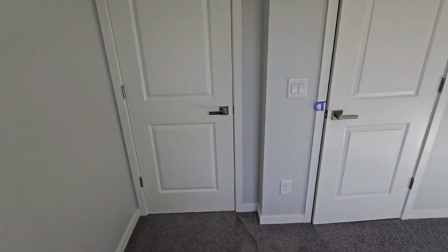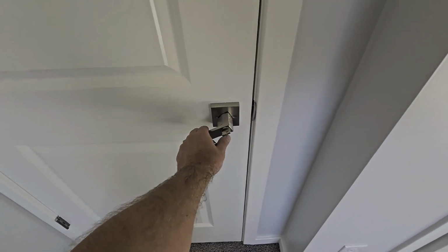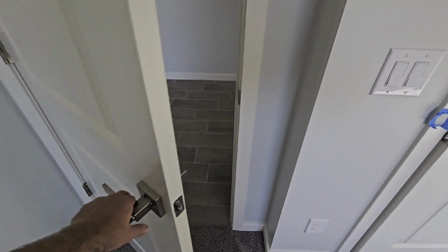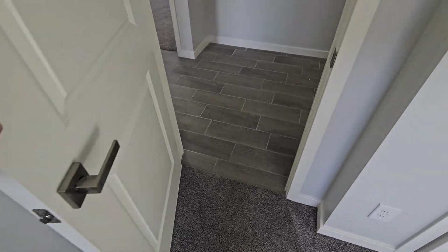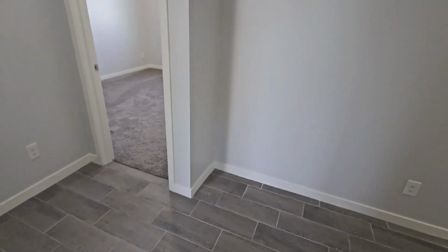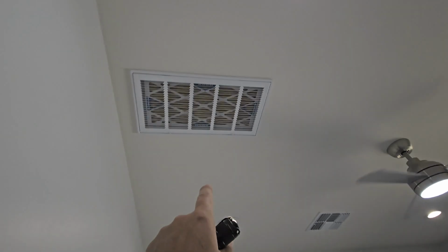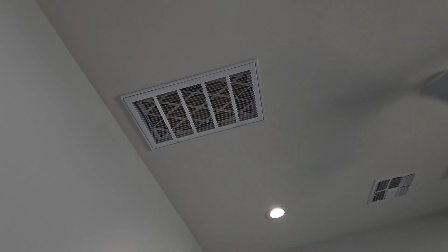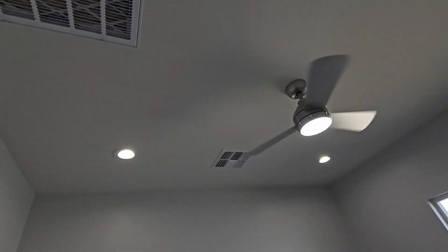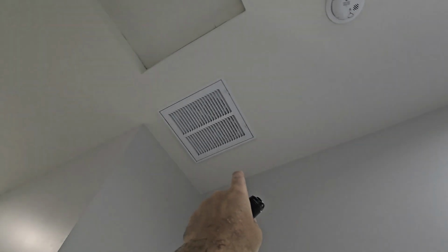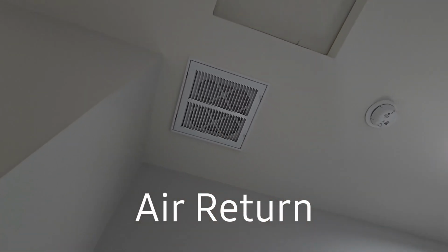This room is going to be pressurized. You're actually going to build up pressure in this room, and it's going to get hard to open this door in the morning probably because of all the pressure you have in here. Then when you release it, all the pressure is going to go back into the house. So what they tried to do, especially in the primary, by putting this extra air return in here, is equalize pressure so you're sucking some of the air out while pumping it in, so you don't have those pressures. Now if it were me, instead of putting this third vent right in the hallway, I would have put two of these in the bedrooms.